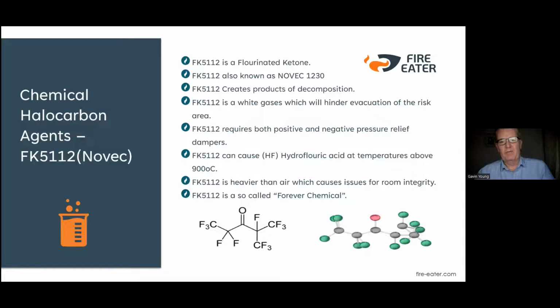It requires both positive and negative pressure relief dampers. Each fire suppression system, be it an inert system or a chemical system, requires pressure relief dampers, because you're putting a volume of gas into the room and an overpressure is created. With Novec, it's both positive and negative pressure, so you need a two-way damper to relieve both types of pressure. It can create, again, hydrofluoric acid at a temperature of 900 degrees C, so it damages your sensitive equipment. It's a lot heavier than air, so in a computer room, for example, that may be quite small, it will be very hard to get the room integrity for that. It's also known now as a forever chemical.